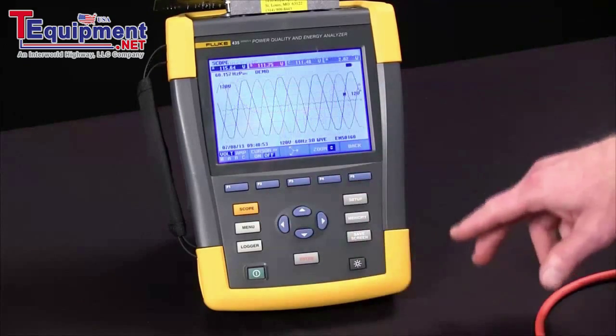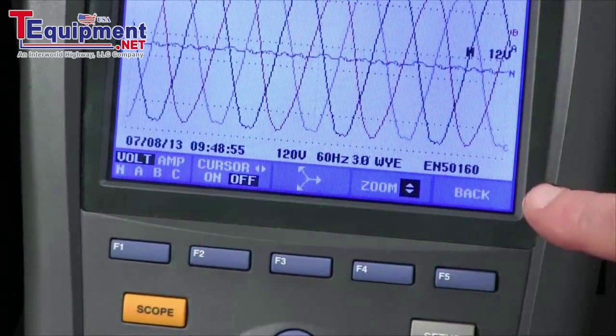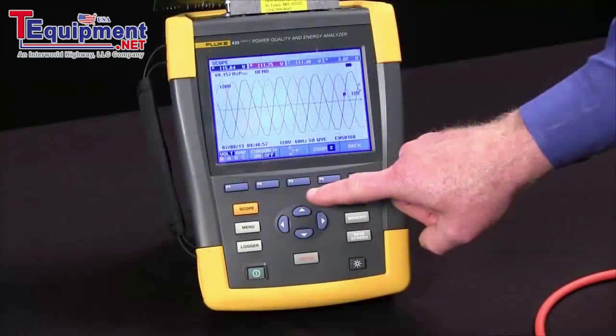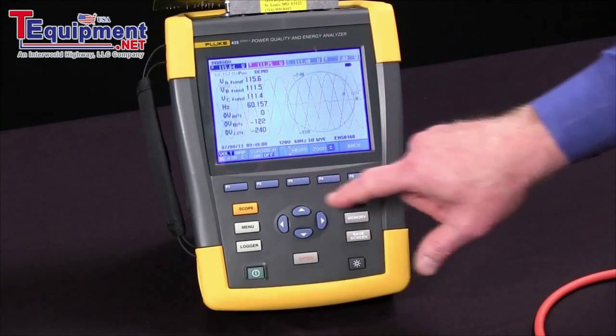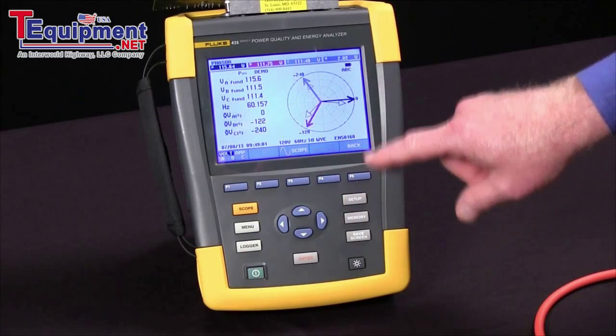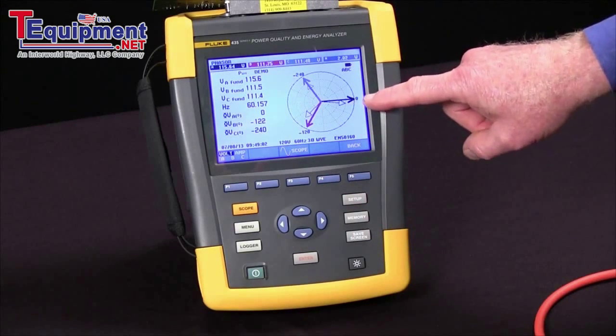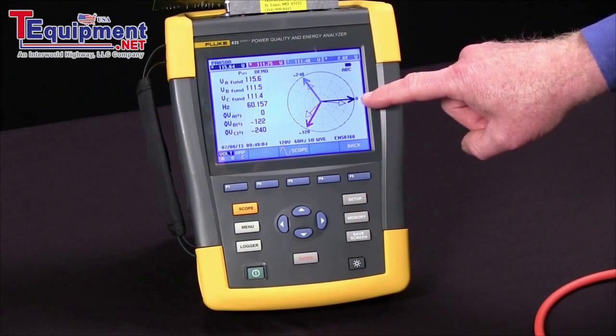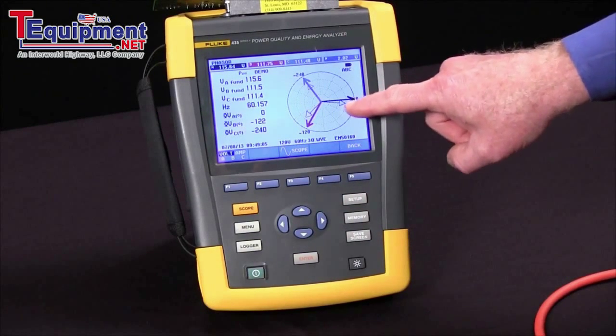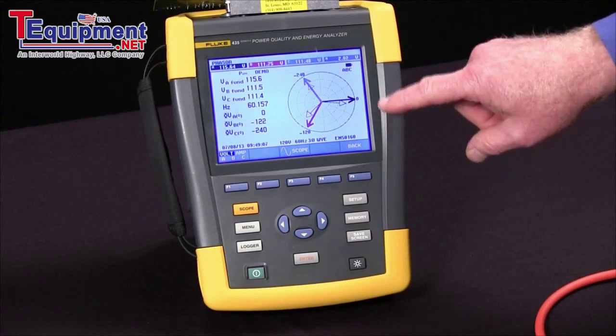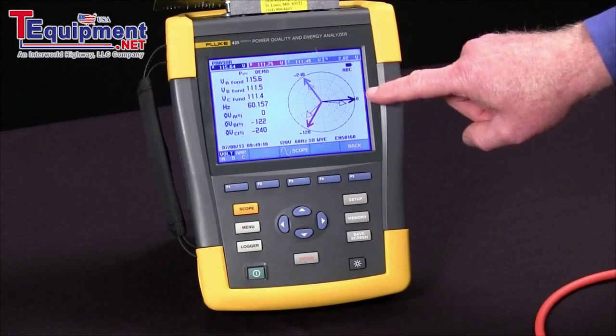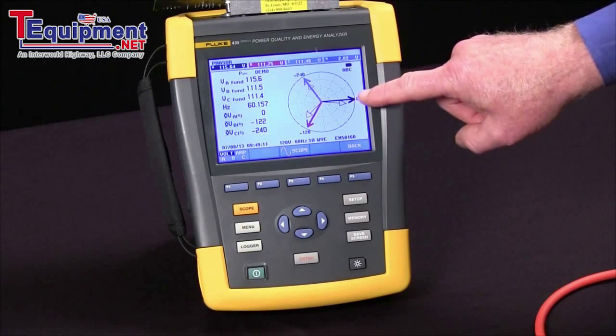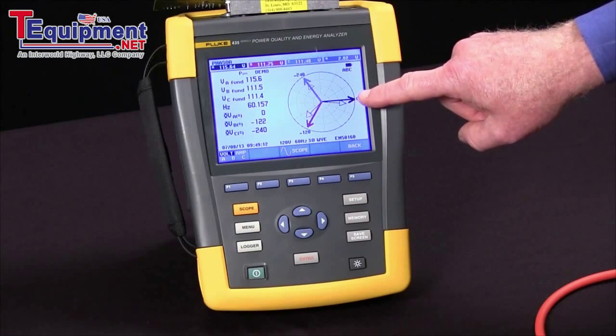we hit the scope key and now we can see our live voltages across the screen. If we use the F3 key to pick up phasor view, we'll see some bold vectors for our voltage and some lighter vectors for our current. If things are properly connected, we should see those vectors being close to in phase with each other.